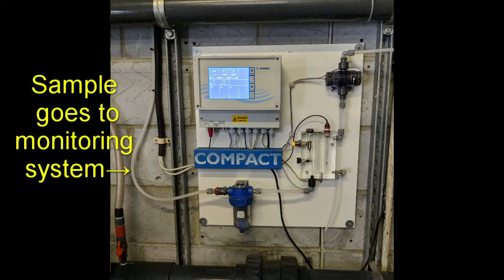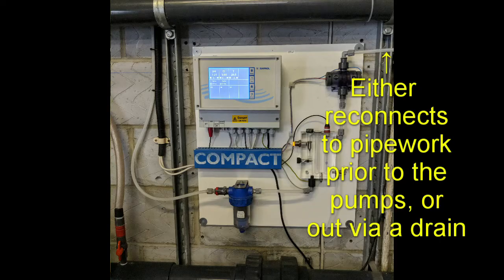And then what you can do is, if you do follow that sample line, and you do indeed find that it's leading to the automatic monitoring equipment, follow that through as well to the point where what you'll probably find is it reconnects to the main circulation pipework on the suction side of the circulation pumps.